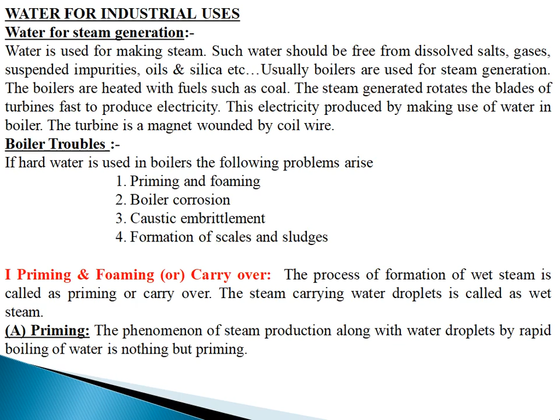This is caused due to high steam velocity, high water level in boilers, improper boiler design, and sudden boiling. There may be some bumping, which leads to priming. Priming can be avoided by maintaining a low water level, fitting mechanical steam purifiers in boilers, and using a well-designed boiler.